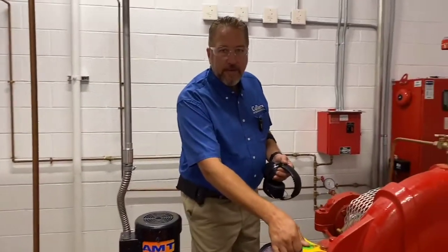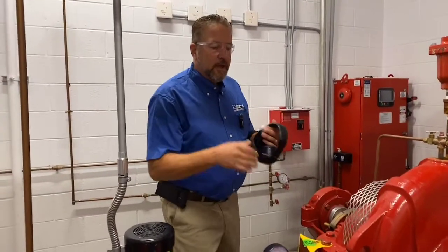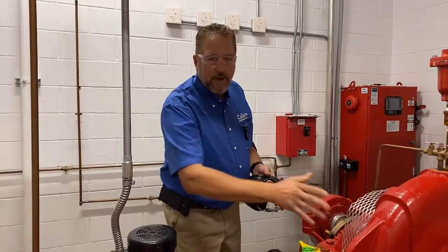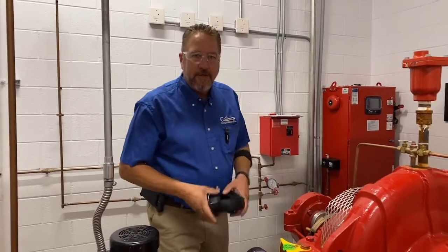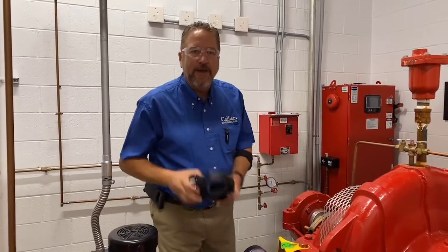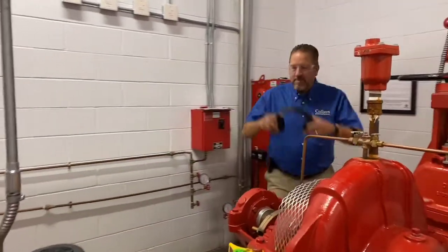Normally you would do a 10-minute fire pump run. I'm going to start it, stop it, so that way I can walk you through and you can actually hear me. You'll see why in a second. Got my handy dandy hearing protection here.